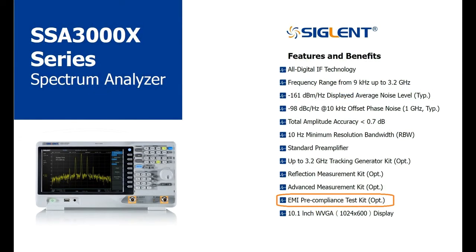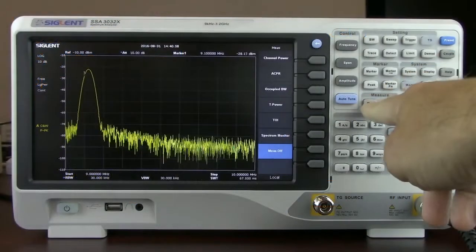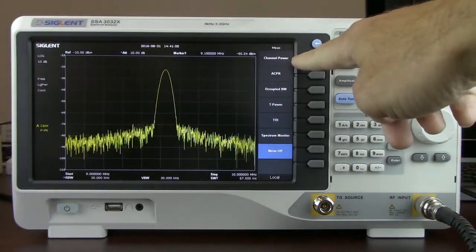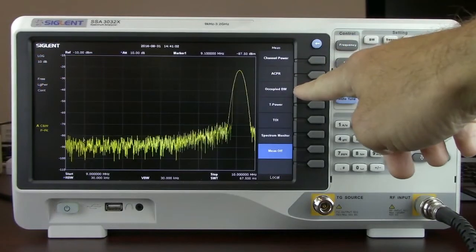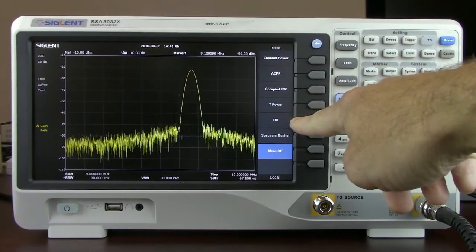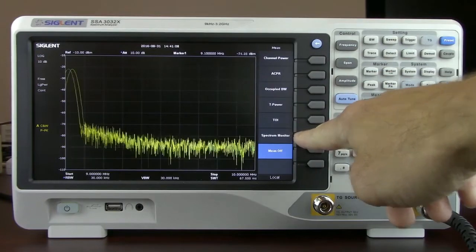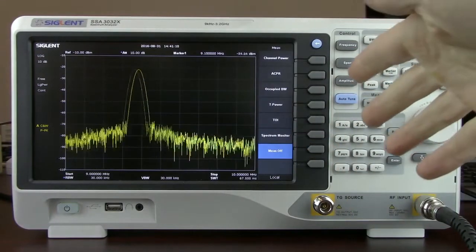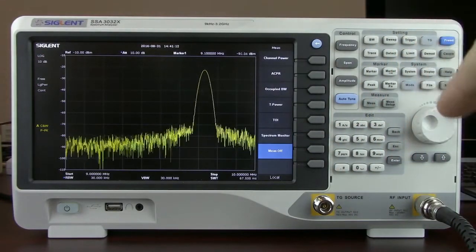The SSA 3000s are also available with the Advanced Measurement Kit or AMK option. The AMK option includes a number of standard measurements used in broadcasting. If we press the measure key, we'll see channel power, adjacent channel power, occupied bandwidth, total power, third order intercept, and spectrum monitor. I'd like to show the spectrum monitor because this is also a feature that isn't available on many other spectrum analyzers.